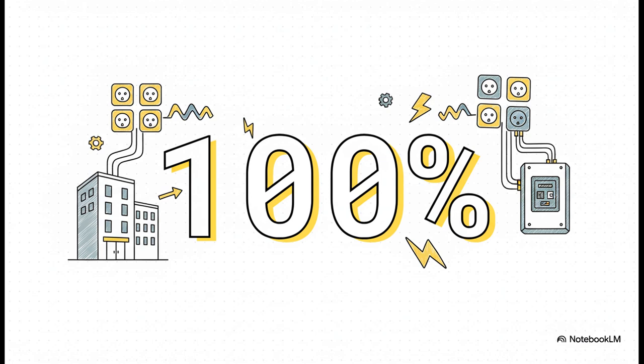Okay, now what's really interesting is how this rule actually starts. The code is still pretty conservative. It says for the first chunk of the total electrical load, specifically the first 10,000 volt amps, you have to account for all of it. 100%, so there's no discount right off the bat.